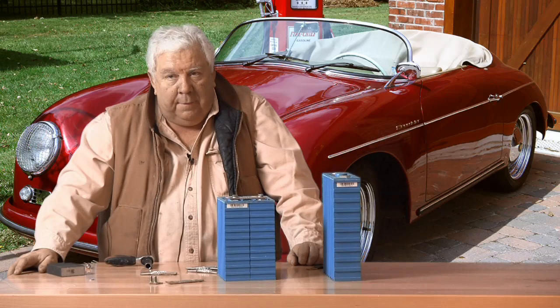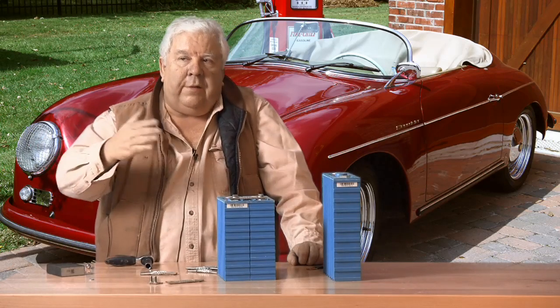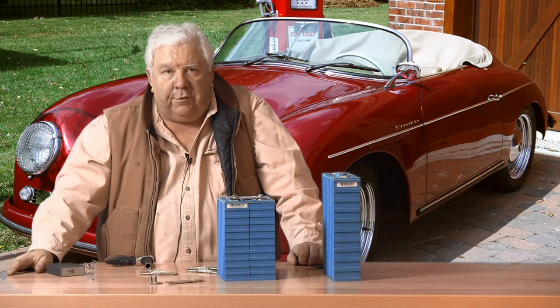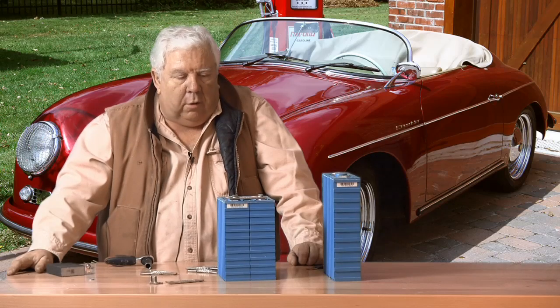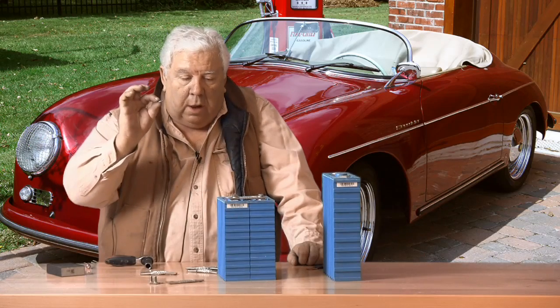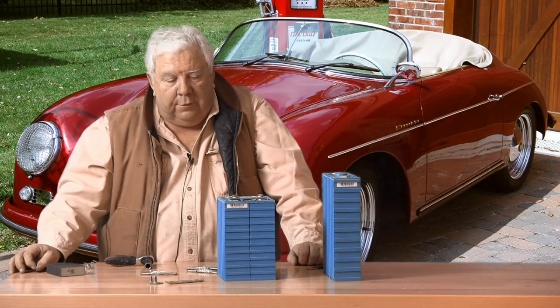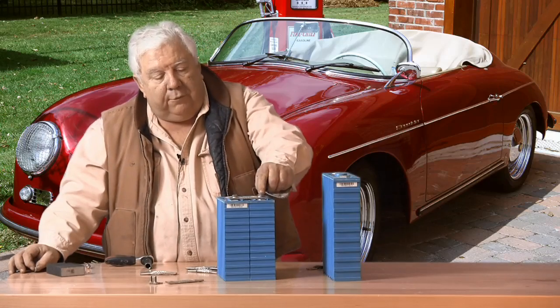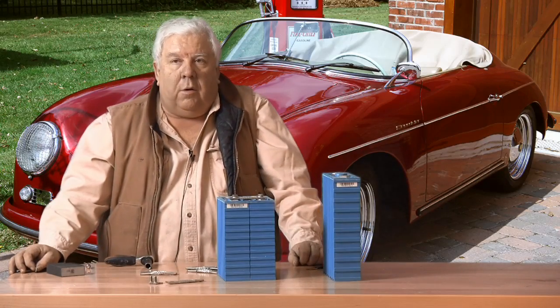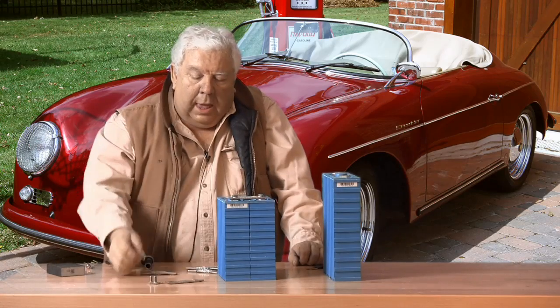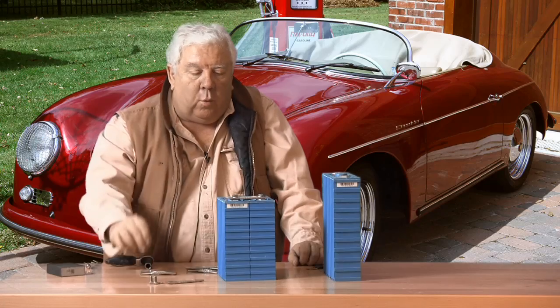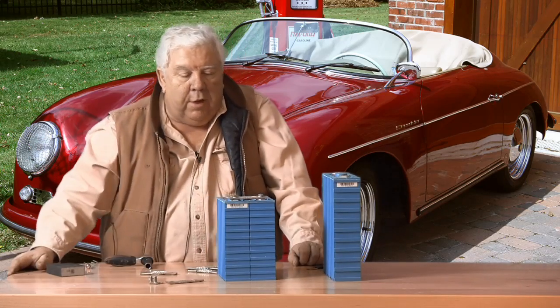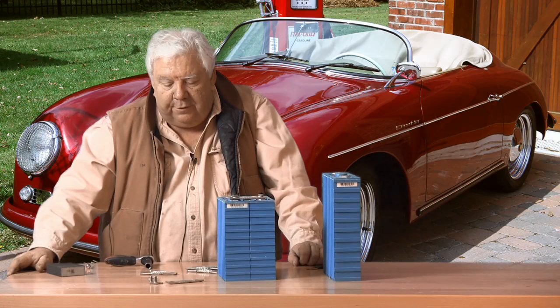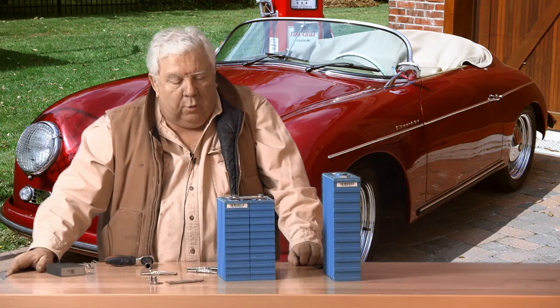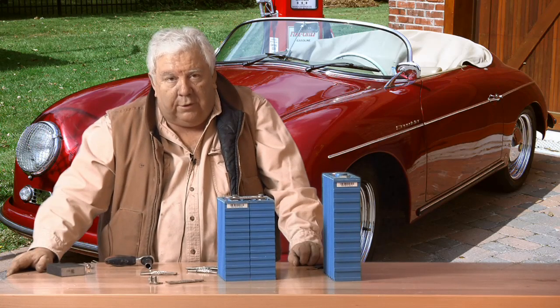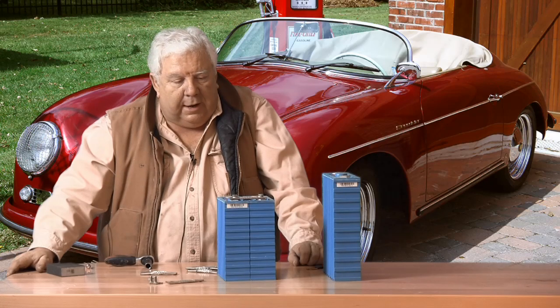It doesn't corrode, for a couple of reasons. One, the strap is tinned, and tin sits between copper and aluminum on the list of active or noble metals. The lowest on that list is zinc, and our Nordlock washer is zinc coated. So if anything in this pile of dissimilar metals is going to corrode due to galvanic action, it will be the sacrificial anode of the zinc washer, not your strap, not your terminals, and not your stainless bolt. That's why we use the zinc-coated Nordlock washers — they really do keep those connections clean and tight.